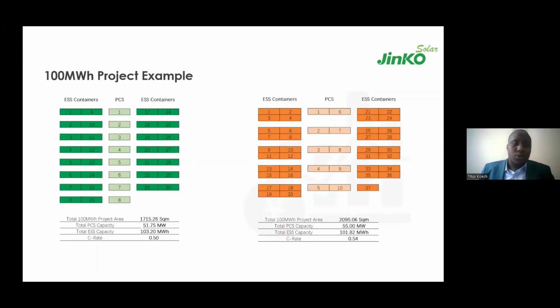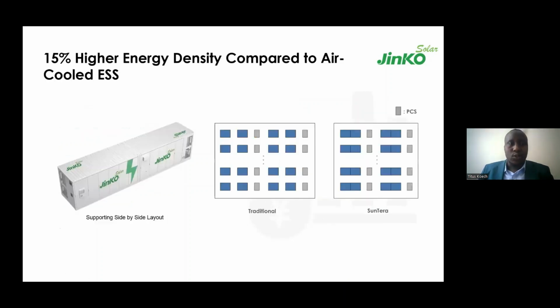For smaller projects, let's say less than 10 megawatts, this might not be significant. But looking at large scale projects, say a 100 megawatt hour project, with traditional energy storage systems we're looking at close to 37 containers, whereas with the SunTera system at 3.44 megawatt hours, we're looking at close to 30 containers. So in terms of shipping costs and the project land area required, we have savings as well.